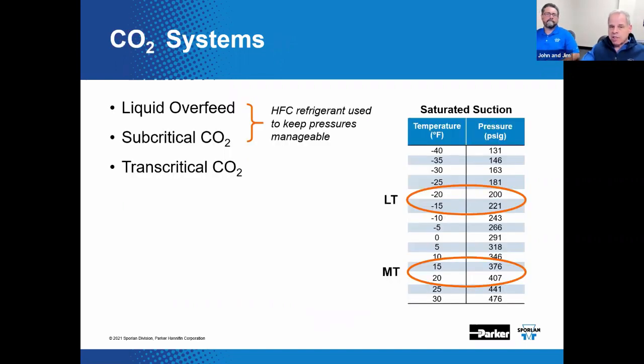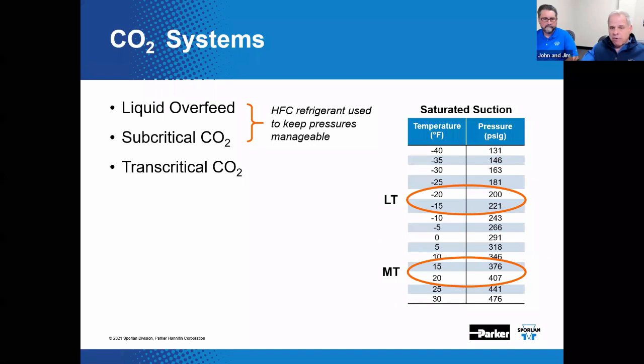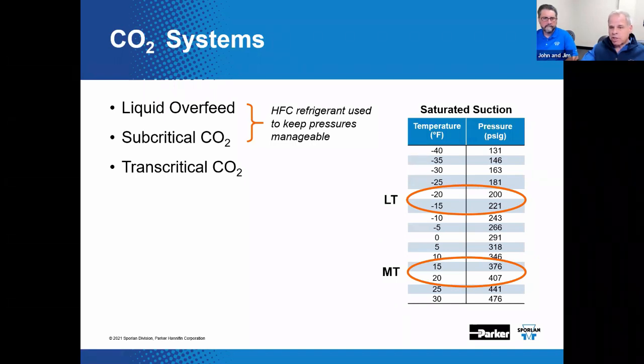Now let's consider CO2. Carbon dioxide, CO2, or as ASHRAE calls it, R744, can be used as a system refrigerant while reducing the HFC charge in a supermarket system. Unfortunately, there is a price to pay for this. CO2 refrigerant pressures are significantly higher than other refrigerants.